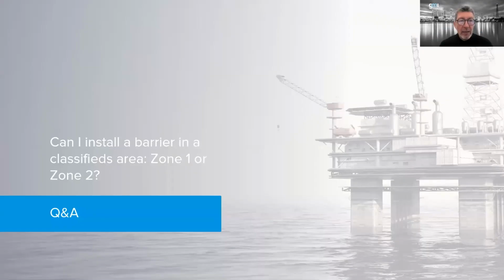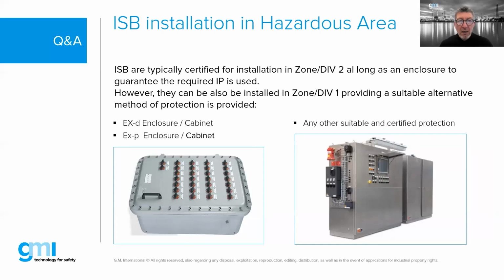So can I install a barrier in a classified area, either zone 1 or zone 2 or div 1, div 2? Here's an answer. Yes, we can. Most barriers that you will find are rated suitable to be installed in a zone 2 area. But if we need to go into a zone 1 area or division 1 area, then we can typically take those associated apparatus and put them inside of other protection concepts, so a flameproof box or a pressurized cabinet.